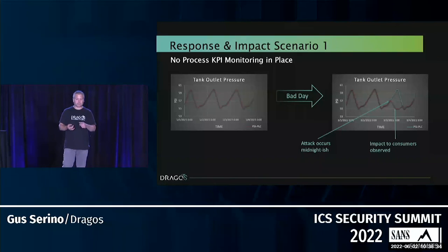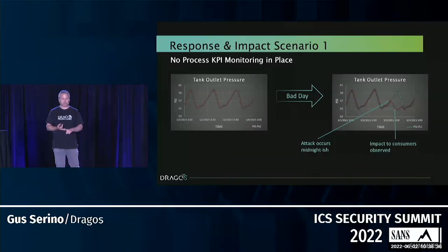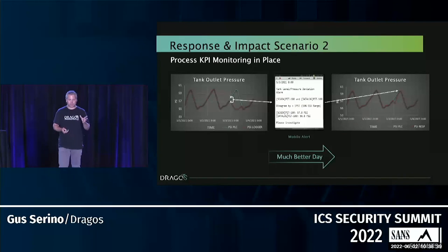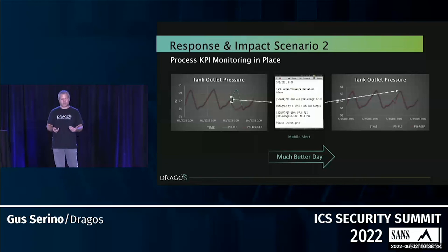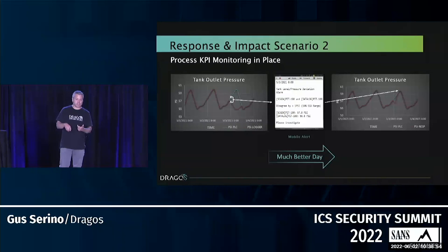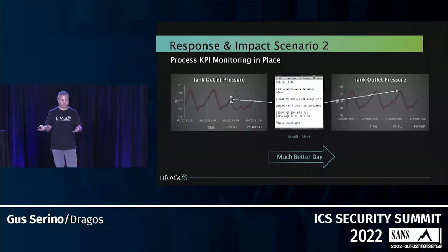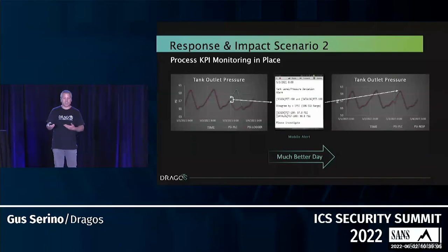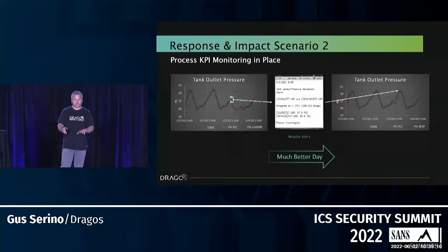With out-of-band monitoring in place, when the pumps stop and the deviation exceeds a threshold, you immediately get a differential alert between what the data logger reads and what the SCADA system is reporting. You can go check it out, confirm the problem, kick in emergency operating procedures, and start filling the tank. Now you're dealing with just a cyber problem — which is enough — rather than simultaneously managing a physical problem affecting the public.